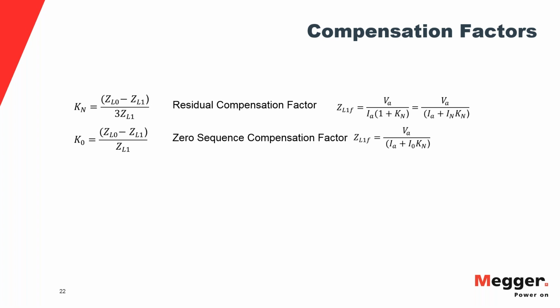Whichever way, because the thing is that different relay manufacturers use different compensation factors. Even the same relay manufacturer uses different compensation factors on different relays. So you have to be aware of that, but the compensation will happen in the relay for the operation of the relay.